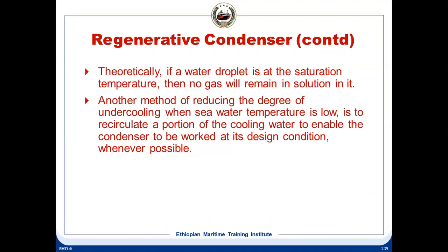Theoretically, if a water droplet is at saturation temperature, then no gas will remain in solution in it. That's the theory. But if any gas is still remaining in the condensate after the regenerative condenser, then we have the deaerator after this, which will take care of any remaining gases as best possible.